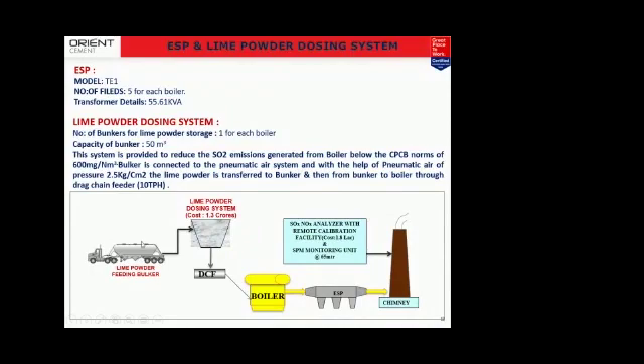As you can see, as we are running a cement plant, we get ready-made dry lime powder from an extraction point where we load it into the bulker, and from the bulker we load it into the lime powder dosing bunkers, each of 50 meter cube.